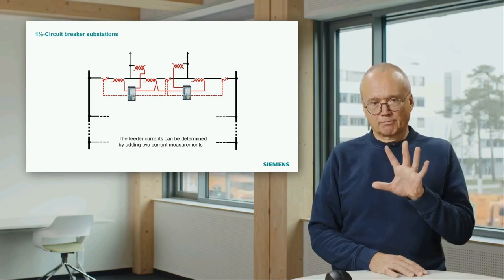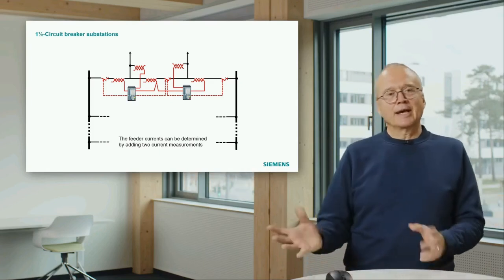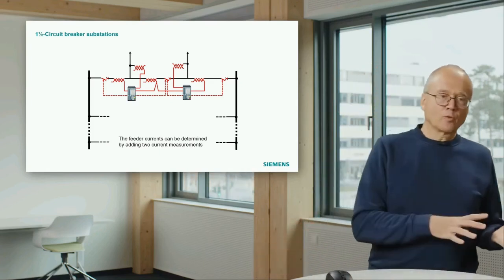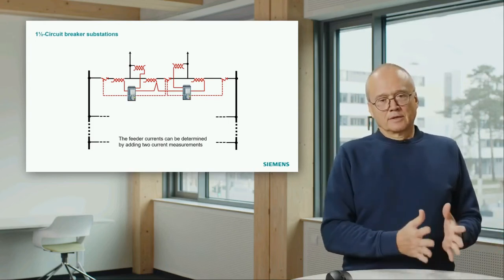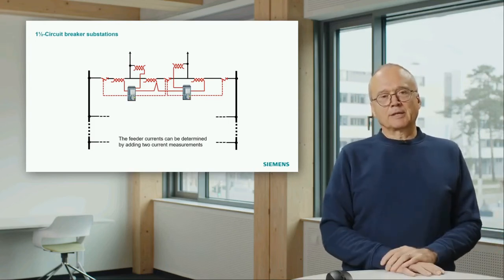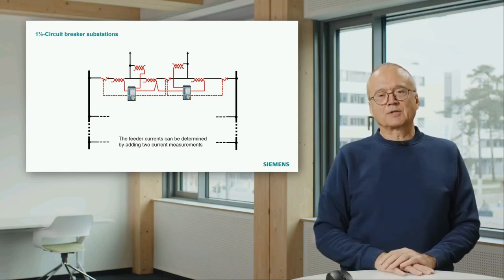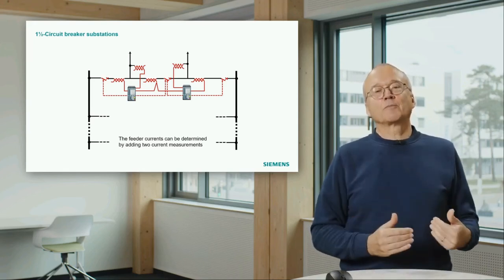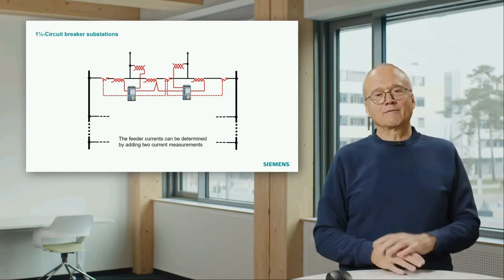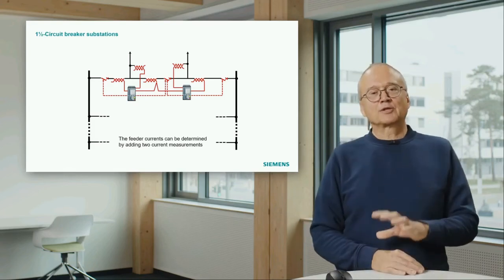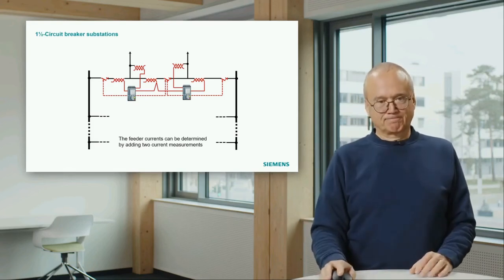This is called breaker and a half substation, and the decision whether we build single line or double busbar substations or such a substation, that comes from the primary system, from the high voltage system. The protection people have to adapt to that.